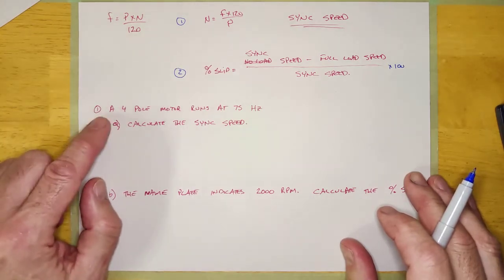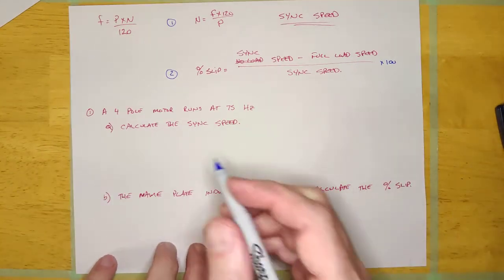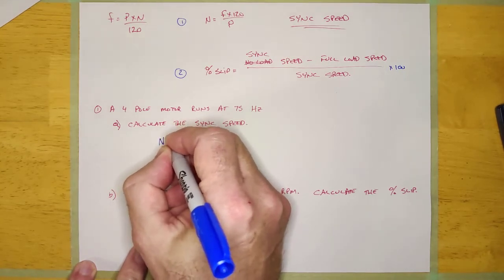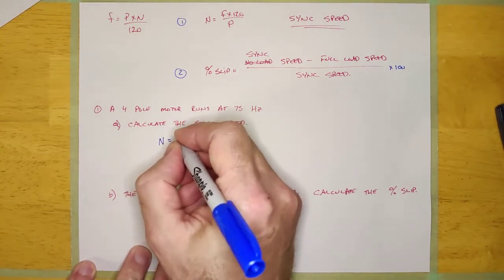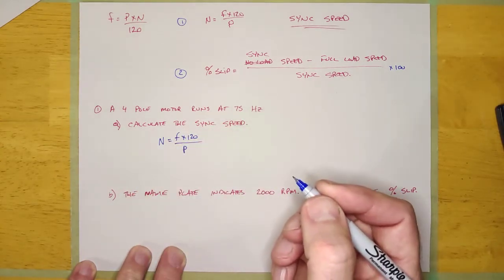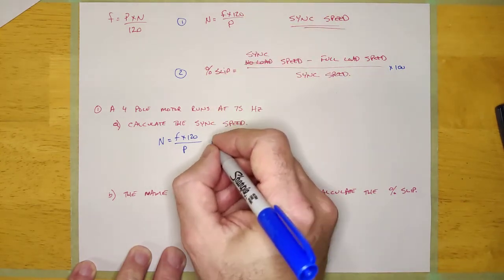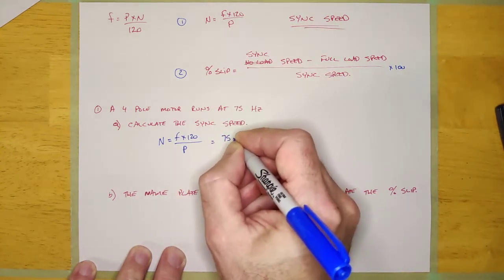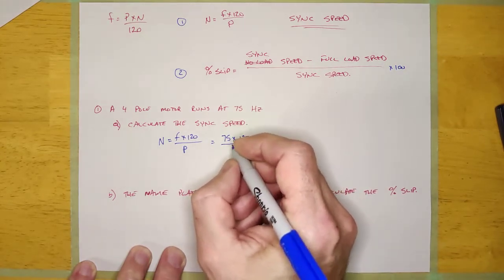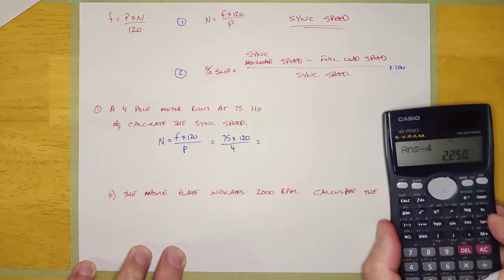So a four-pole motor runs at 75 hertz. It says calculate the sync speed. Well, let's calculate the sync speed. The formula is N, which is speed, is equal to F times 120 over P, which is the number of poles. And so the frequency is 75, guys, and 120 is just a constant. And P stands for the number of poles, which is four. And if I calculate that, let's do it right here.